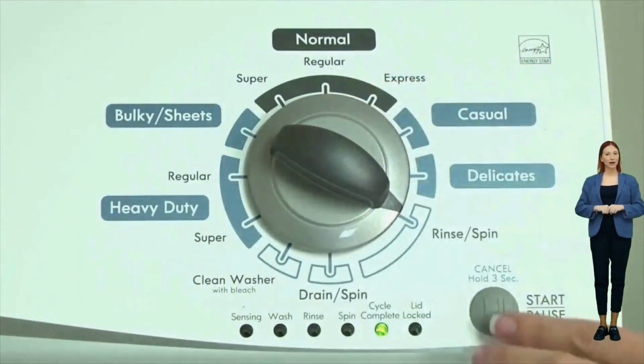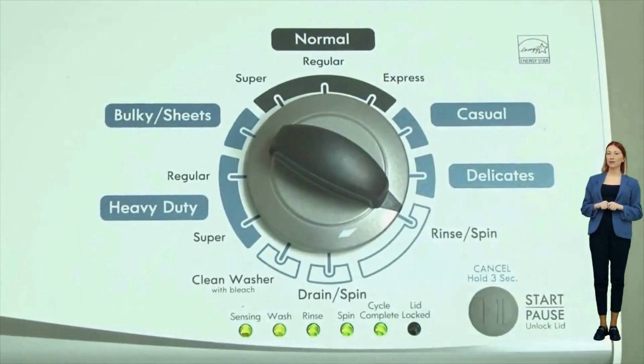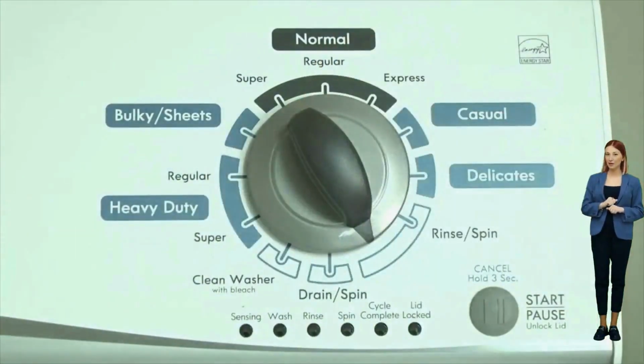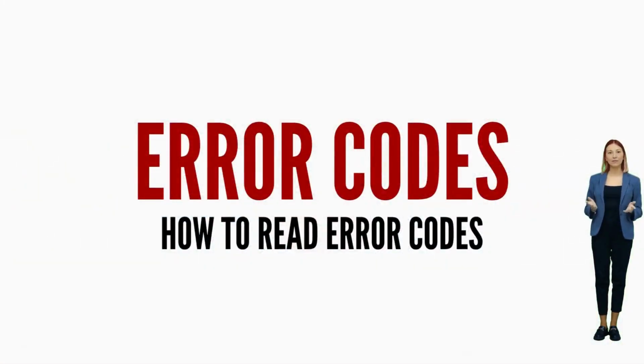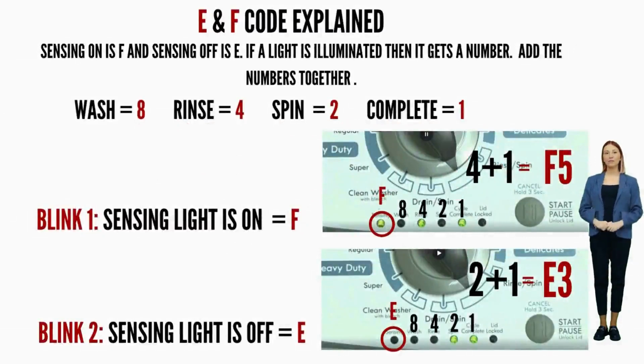This reveals the first pair of error codes. Each code has 2 parts, an F, followed by a number, and an E, followed by another number. The letters and numbers are represented by different lights being on or off. Get a piece of paper and write on one line, sensing light on equals F. On the next line write, sensing light off equals E. Then each line after that put.